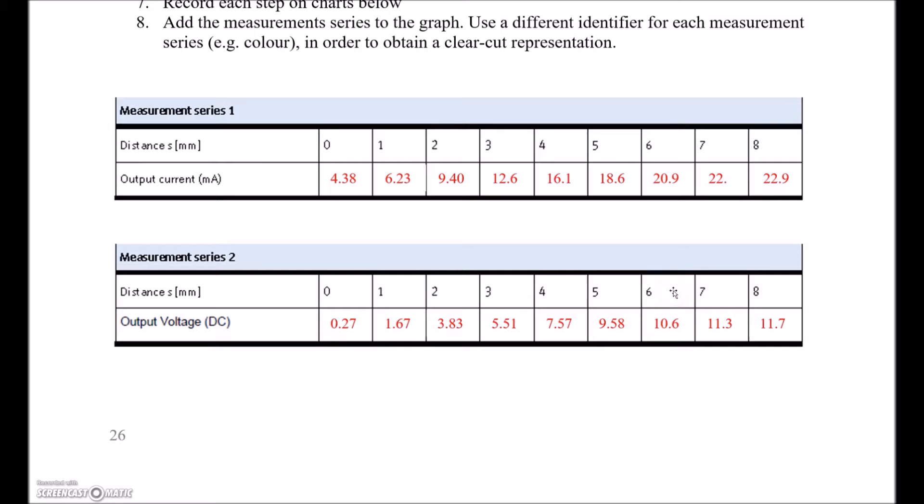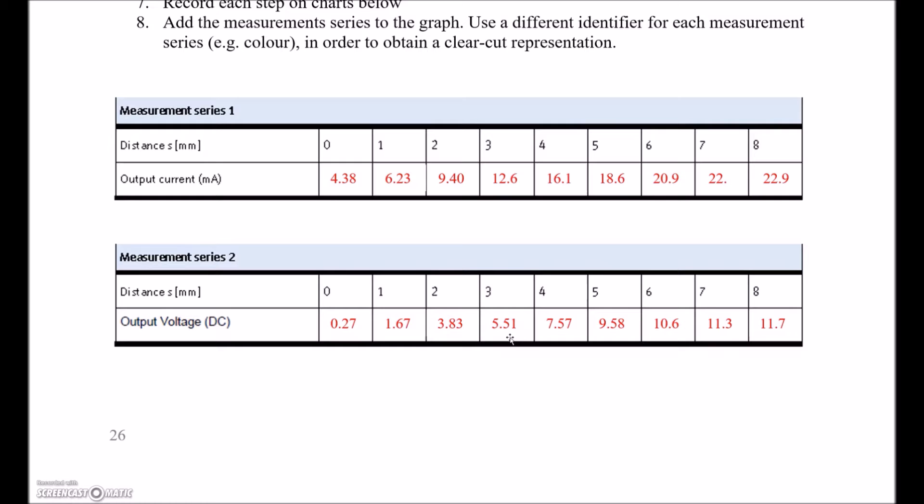Half of that would be 3 mils giving us half of that voltage. Not exactly perfect, but pretty good for looking at the distance of the object in front of this sensor. So it's providing a varying output based on how close the piece of steel is close to your inductive sensor.